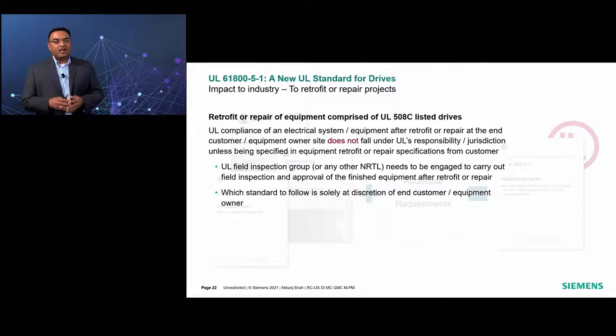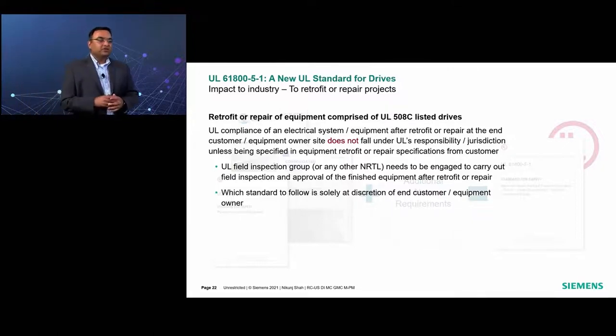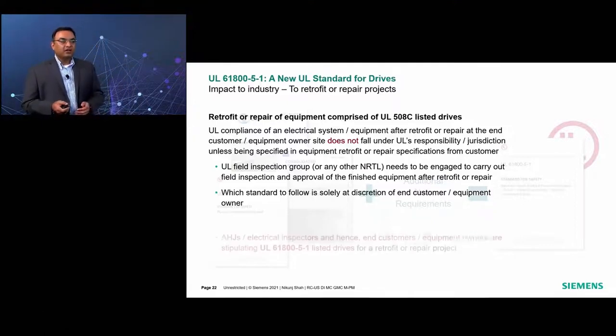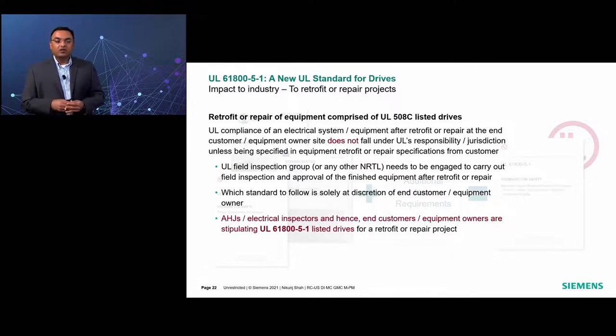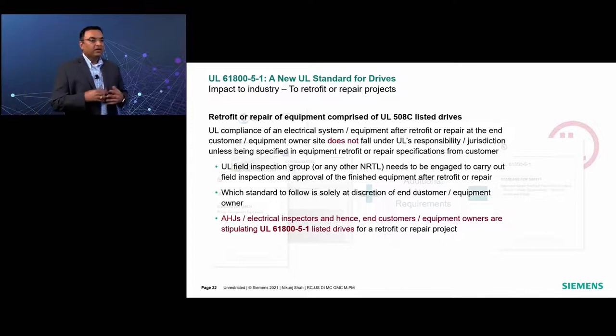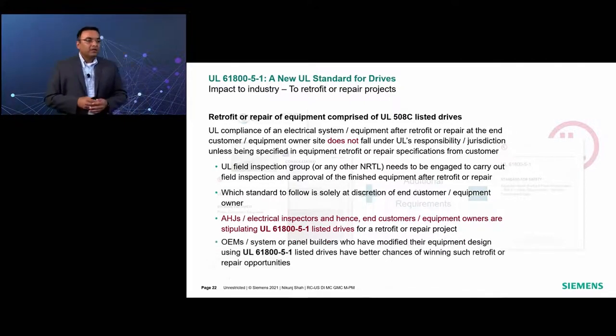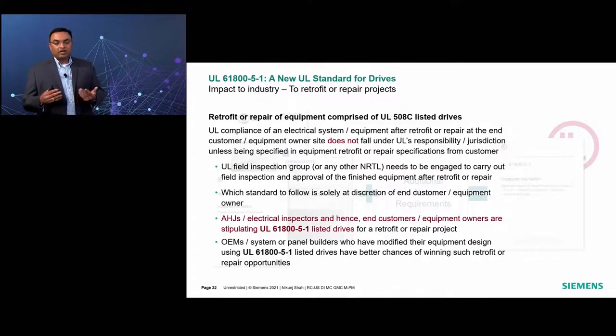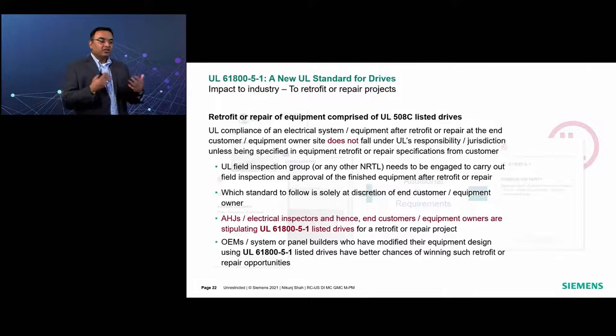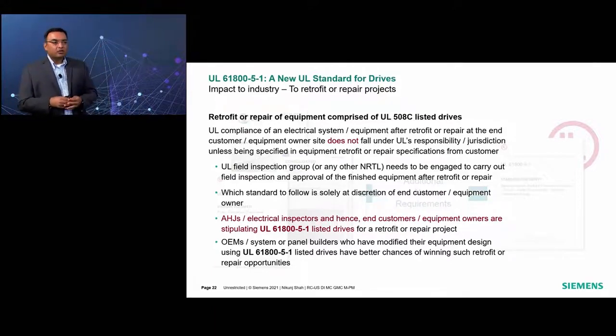At that point, which standard to follow is solely a choice of the customer or equipment owner. But most likely they are going to specify, or have actually started specifying, 61800-5-1, especially because the authorities having jurisdiction, the electrical inspectors, have started mandating the use of drives which are listed only according to this new standard. Therefore, the customers and equipment owners are also stipulating drives which are certified according to 61800-5-1 for retrofit and repair jobs. The OEMs and panel builders who are proactive, like I mentioned, and who have made these changes in their equipment and replaced the old 508C drive with equivalent 61800-5-1 listed drives, are in a better position and have better chances of winning such retrofit or repair opportunities now.